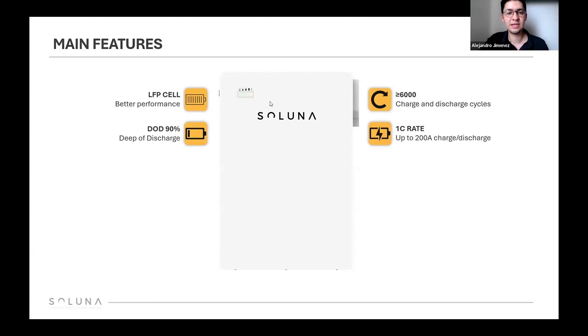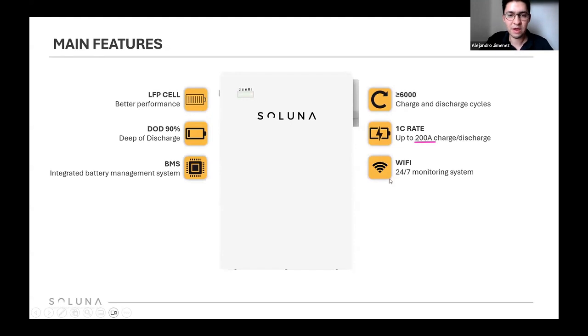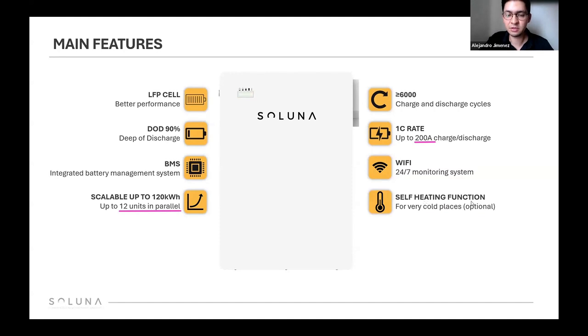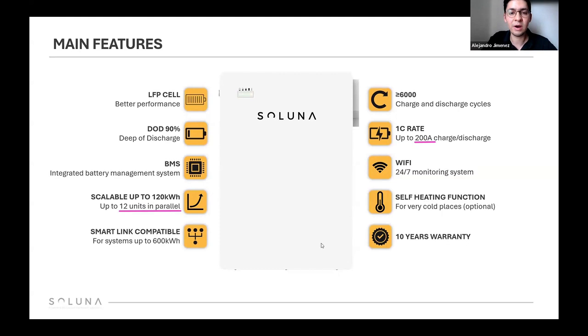1C rate, in this case for low voltage, we can work with more current, up to 200 amps for discharge. BMS integrated, Wi-Fi monitoring, scalable up to 120 kilowatt hours in this case with 12 units in parallel. Self-heating function, optional as I said before. SmartLink compatible — we'll see the SmartLink in the next slide, but the SmartLink device can work with either HV or LV batteries. It's the same device and can work with both battery solutions. 10 years warranty.